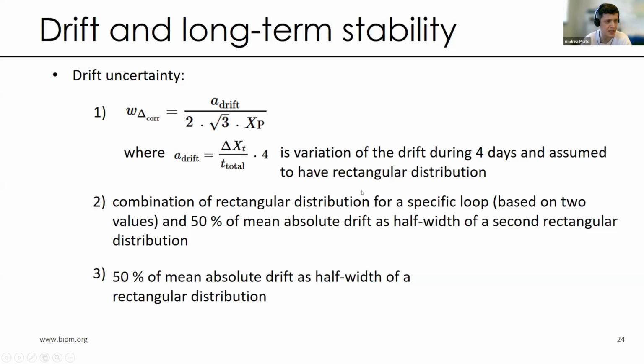rectangular distribution is associated with a specific loop, so based on two values. And another part of uncertainty is considered as 50% of the mean absolute drift, which corresponds to half width of this second rectangular distribution. So by combining these two terms, we can associate an uncertainty due to drift. In particular, these 2 and 3 options are considered when no correction is applied.